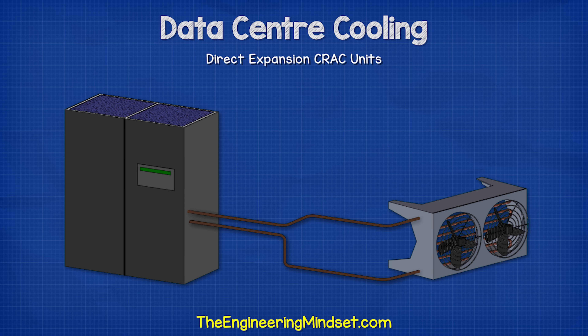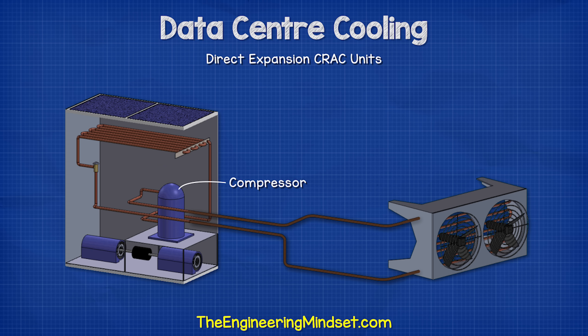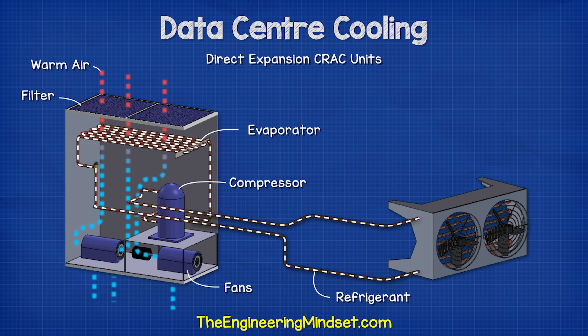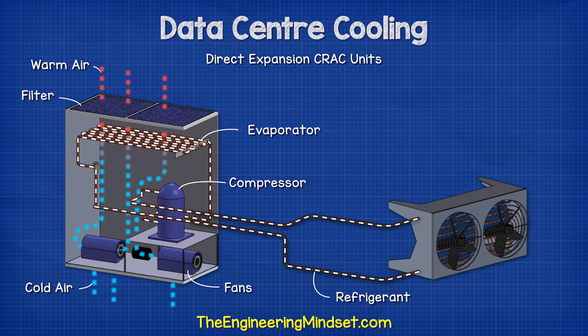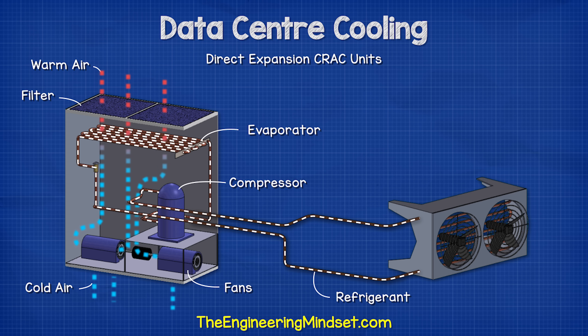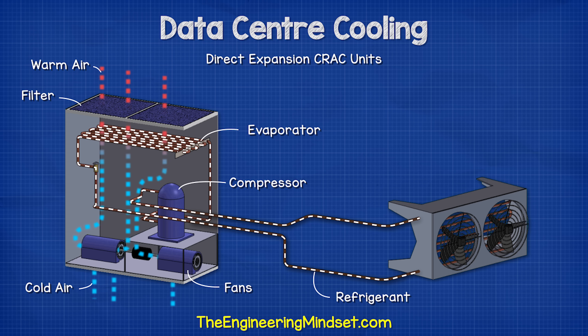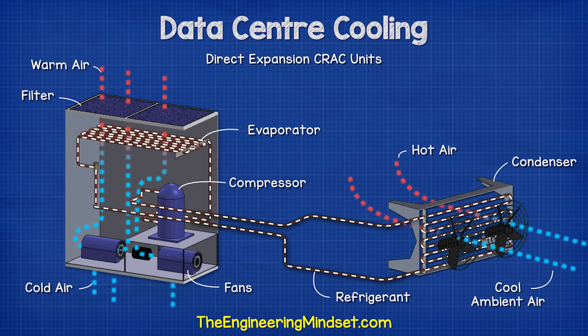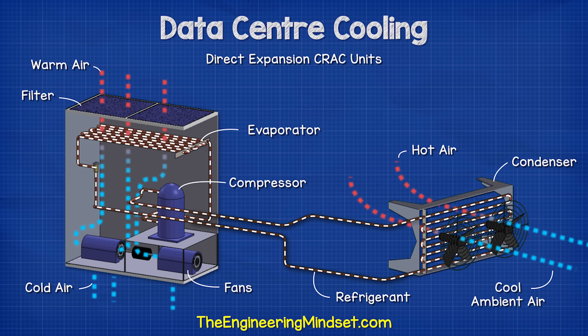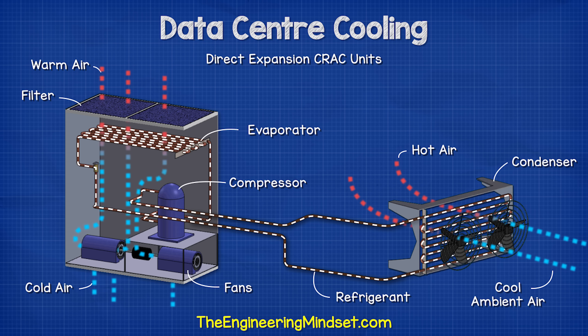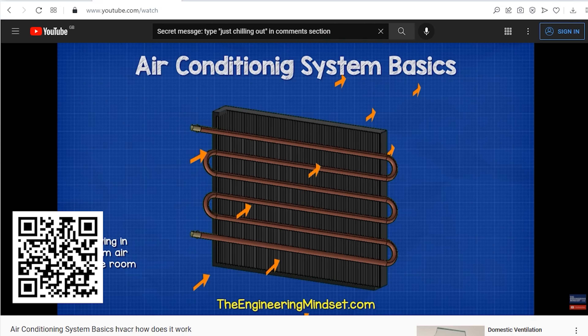Smaller data centers will often use direct expansion units where an internal compressor pushes refrigerant around the system. A fan moves the hot air over a heat exchanger known as the evaporator. The refrigerant flowing inside the evaporator absorbs this heat, so the air leaves cooler and is pushed into the void under the floor. The refrigerant flows to the condenser unit located outside, where a fan blows air over the pipes to remove the heat from the system. The refrigerant then returns to collect more thermal energy. We have covered the basics of refrigeration systems in detail previously — I'll leave a link in the video description down below.